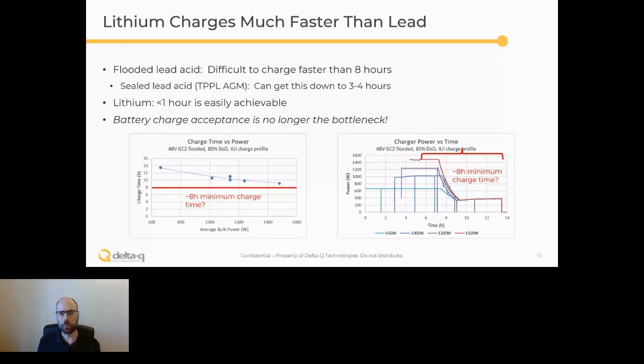Now, with sealed lead acid, particularly with thin plate pure lead AGM, those thin plates give it higher surface area, so it has higher power and higher charge acceptance. Those can be charged at higher rates, and maybe it's possible to get this down to 4 hours or so. But that'll still depend on the charge profile and what you end up doing at end of charge.